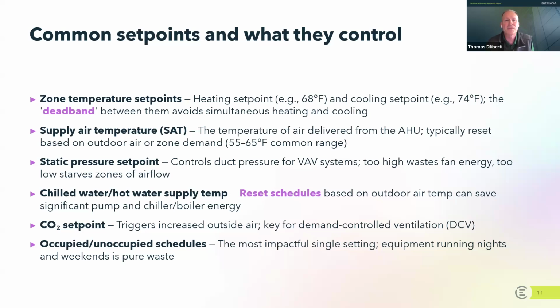But that's the concept of a dead band, and one that's applied across building automation systems in many ways, where there's a range of temperature or set points where nothing happens. The building just coasts. And maybe that's the best way of thinking about it, where the building is coasting rather than aggressively heating or cooling. So, long explanation there on deadband.